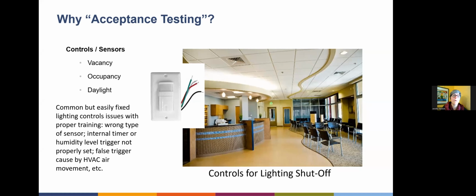So why is acceptance testing required? One of the acceptance tests is for the actual controls on lighting systems - day lighting controls, occupancy controls, vacancy controls. It's really common, but easily fixed, to have issues with some of these controls. In this particular building, it was commissioned before acceptance testing was required, which tells us why we need acceptance testing now.